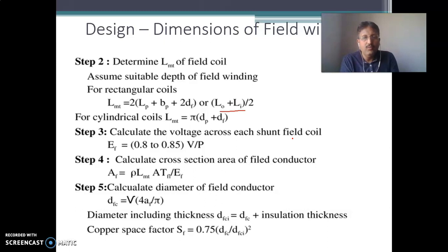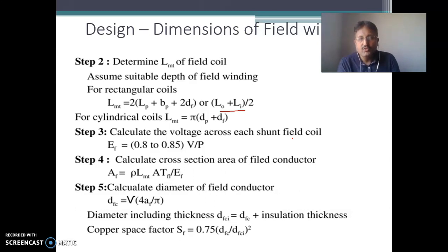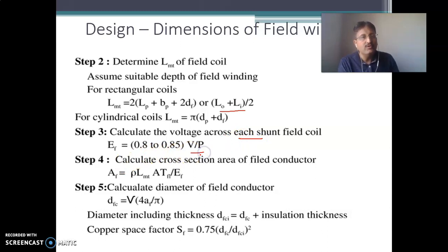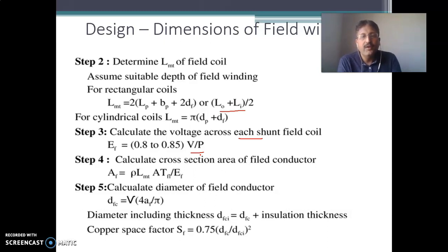To find out the voltage across each shunt field coil: the total excitation voltage is V. We consider 80 to 85 percent of that voltage — 0.8V or 0.85V — which gives the voltage across all the field coils. Since all field coils are distributed across the number of poles, the voltage across each shunt field coil is divided by the number of poles. The remaining 10 to 15 percent voltage is across the field regulator.